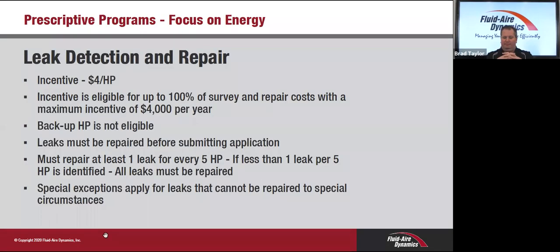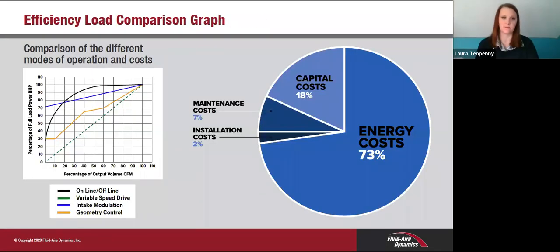Anything you'd like to add, Laura? No, I think that was a great point. It's not uncommon for a lot of equipment to not be the right size for every single moment, and you have to have it sized for that busiest time of the day to have the available air. But like you said, different shifts, or even within the same shift, you may have different periods of time where you're not really consuming full or near full capacity of where that equipment would normally operate at its most efficient. So most of the time you're at that part load, and if you can match that by using a variable speed compressor, you have the ability to save a lot of energy.